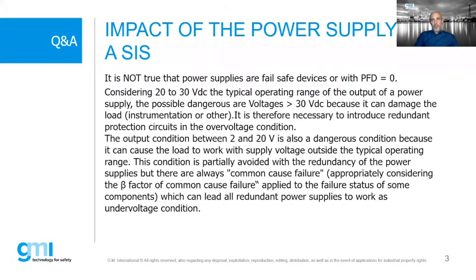Okay. So we are talking about the power supply and fail-safe, for people that aren't familiar with this terminology. Fail-safe is a characteristic of a particular device which causes the device to move to a safe state when it loses power. But power supplies, as Massimo explained in the previous slides, can fail in different ways. So we can say that 20 to 30 volts is the typical range where the power supply is working. And the dangerous condition, as we remember, is when the voltage is higher than 30 volts, because this power can damage the instrumentation of the system you are powering.